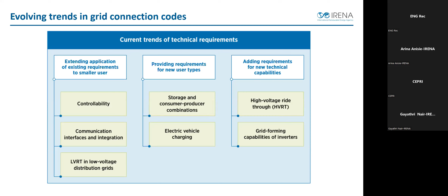Next slide, please. So controllability. From this slide onwards, I'll try to highlight some examples. Some examples here regarding controllability show how, like I mentioned before, power reduction or power increase capabilities can be required for newer additions to the system or active participants in the system. And mostly, this is usually specified to the extent possible without mandating an addition of energy storage. While the VRE share is very low in the system, these active power management capabilities may not be needed, but this changes quickly as the share of VRE increases. So there is no downside to making this a requirement from the very beginning. So you can see the example.